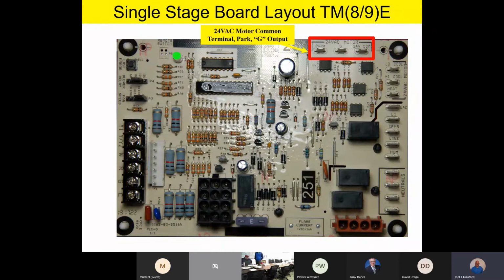So moving around the board, remember, team, this is an ECM type of motor, a high efficiency motor. So the way this motor works is we're going to have power to it all the time. So anytime there's power to the furnace, there's going to be 115 volt to the motor itself. But the motor's just sitting there waiting for 24 volt commands. And so this is where we're going to start showing you how we're going to control that motor with 24 volt commands. So where it says 24 volt AC motor, on those terminals up there, you're going to find a park terminal for any unused motor taps that you're not using. That's where you'll put it, on the park terminal.